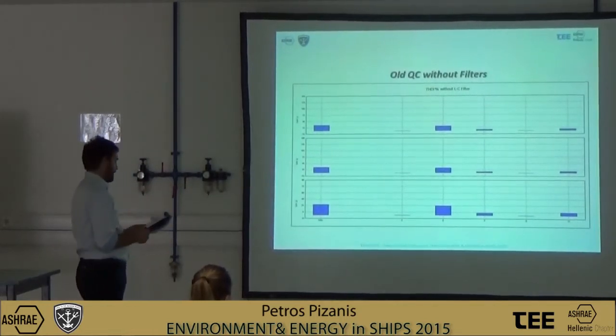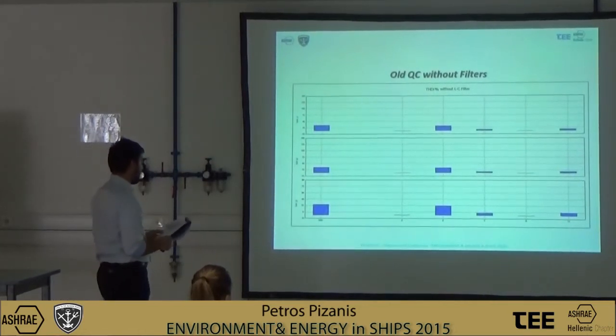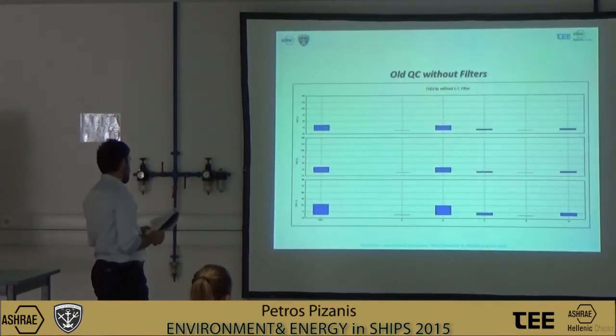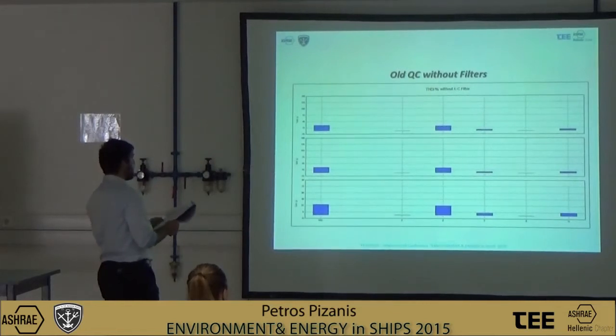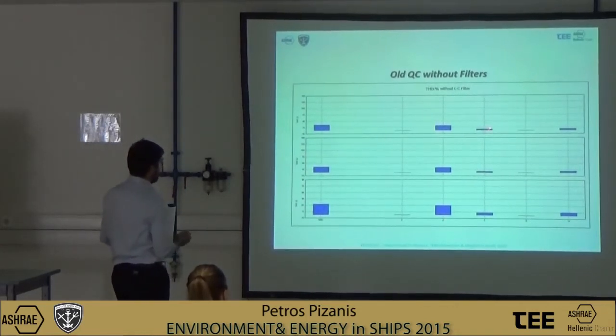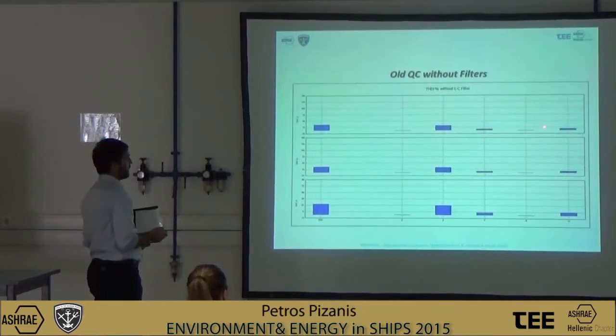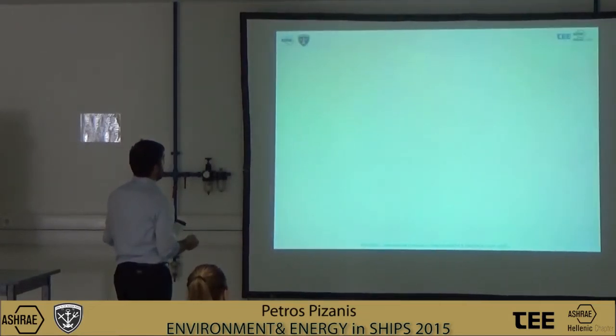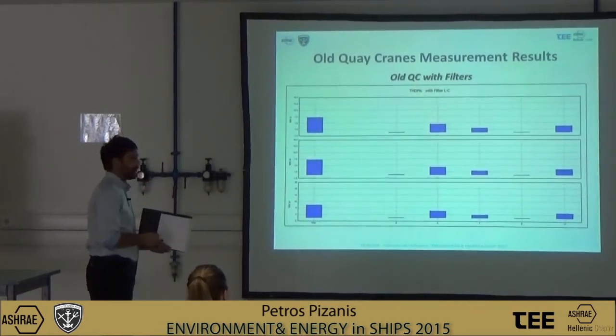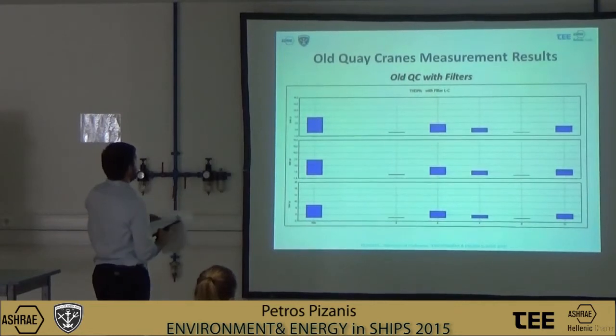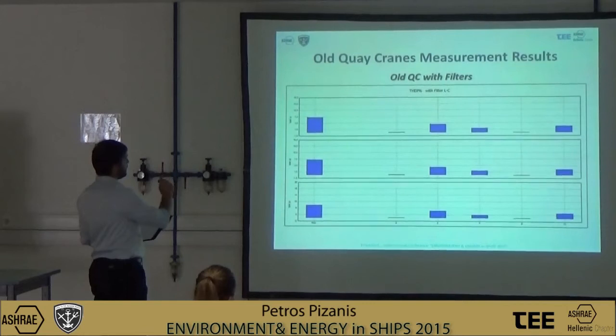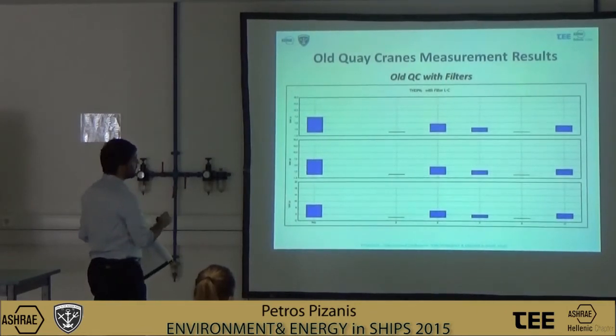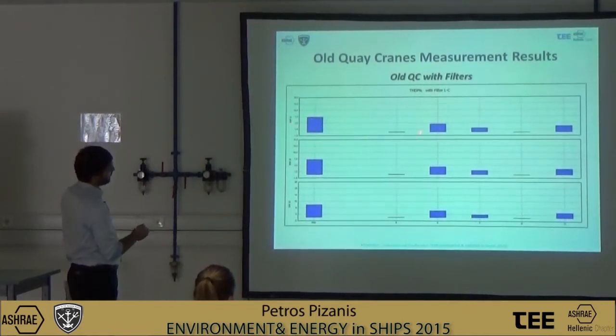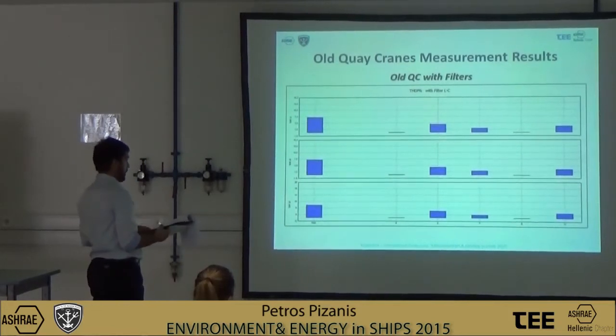In old crane technology, there were no harmonic filters installed. When the company I work for first commenced operation at the port, they decided to install these filters so the crane will be more efficient towards the environment and also to reduce the electricity bills and penalties from the power supply company. As you can see in these pictures, with filters, the harmonic waveforms are very small compared to the next slide. Those are the harmonics, 3rd, 5th, 7th, 9th, and 11th. Compared to the next slide, which shows an old QC without filters, we can see that the increase is much bigger. Unfortunately, it's difficult to notice the difference here because you cannot interfere with the logger data. The scale here is 3 times more than the last one without filters.